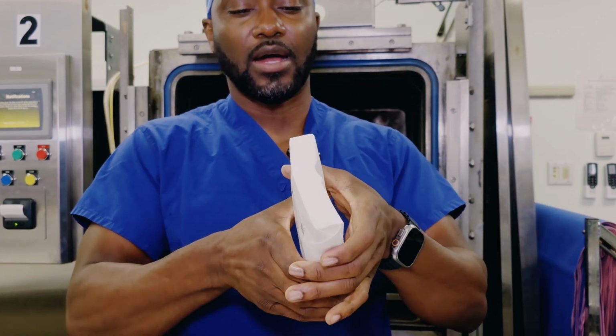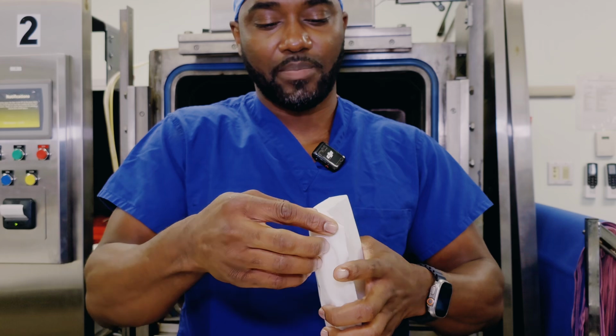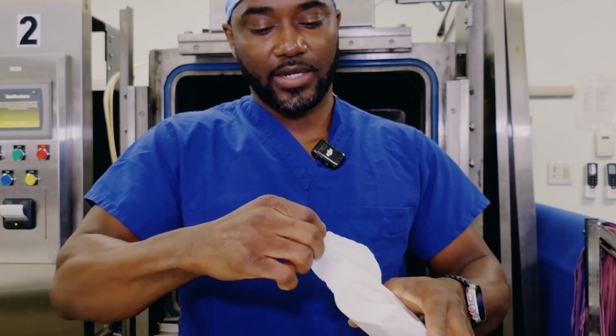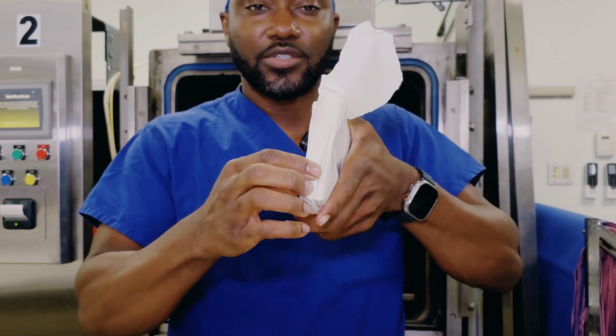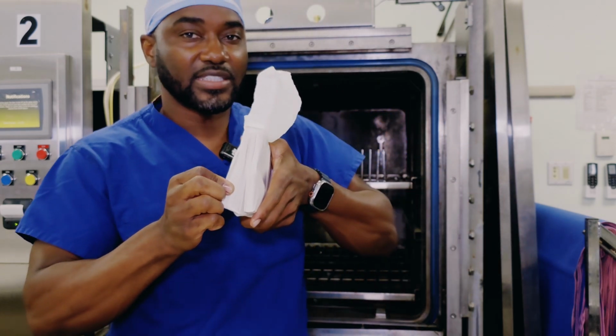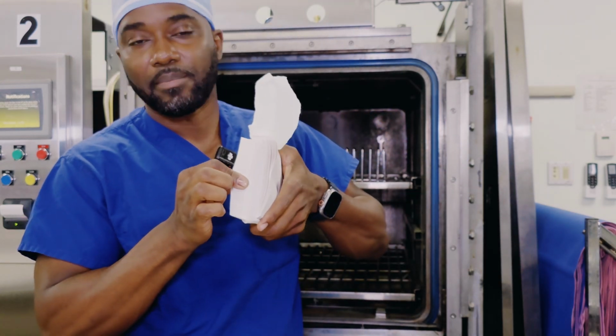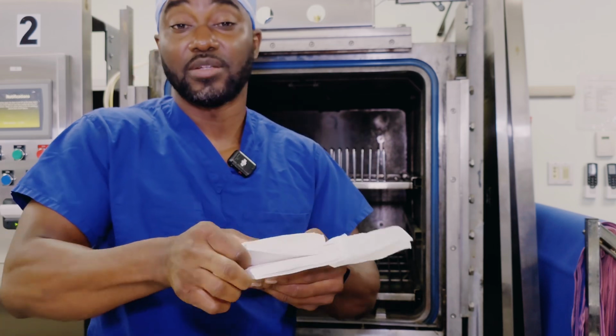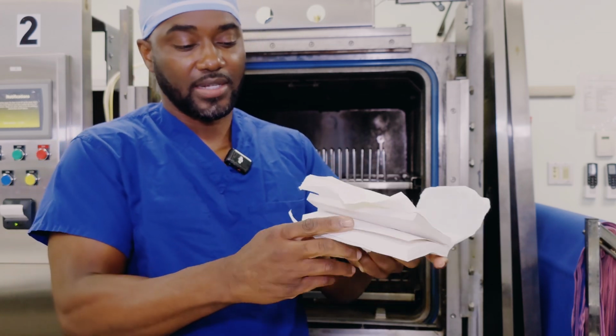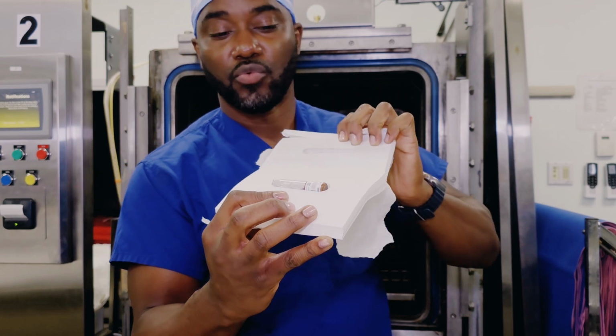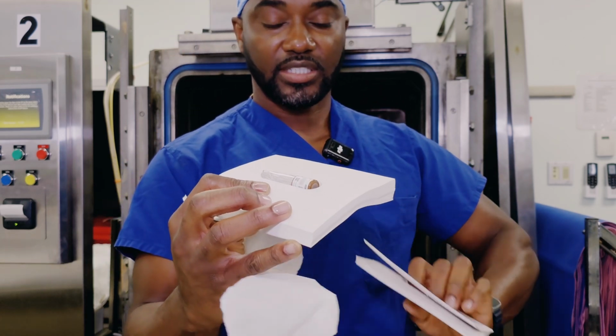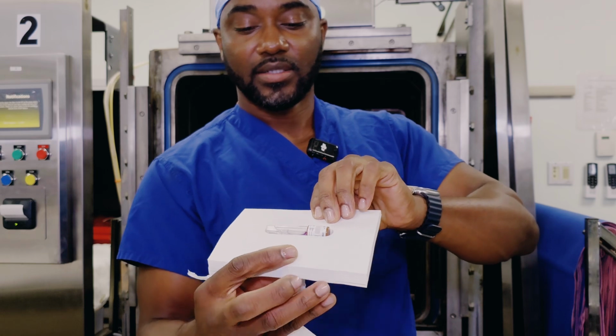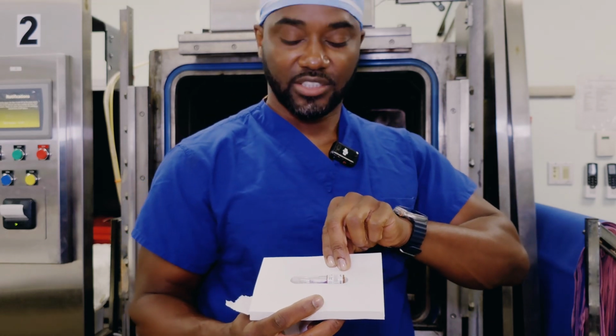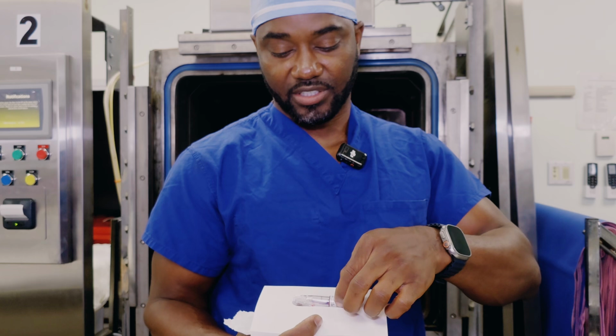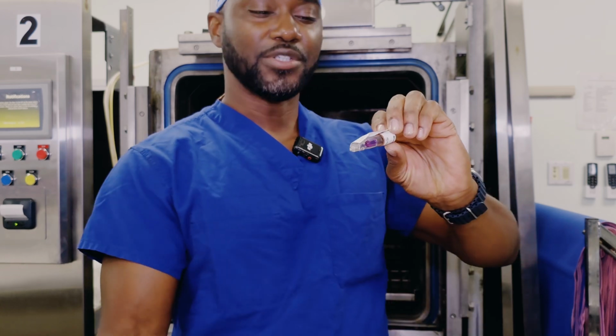So let's pop this open. And I want you to see on the side how thick of a paper that is, which makes it very challenging for steam to actually enter. Do you see the thickness of this paper over here? This is how thick it is. Imagine steam penetrating this packet just to get into the middle of this packet to change the color. What's on the inside? You see this ampoule, which is impregnated with a Geobacillus spore. This is what's inside of this packet. This is why it's called a process challenge device, because you want this to challenge the efficacy of the steam sterilizer. Do you notice the chemical integrating indicator in here?